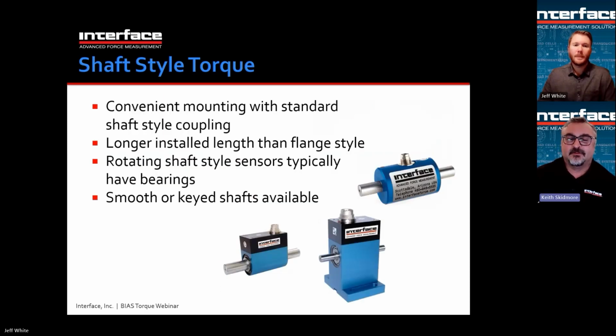So shaft style, as we said, has convenient mounting with standard shaft style couplings. Shaft style couplings are readily available. And again, there are plenty to choose from that have a gripping feature so that they grip onto the smooth shaft and then can be released later. These are typically longer, as we said, than flange style sensors. They typically have bearings, and again, can either be smooth or keyed shafts. The examples here all show smooth shafts.